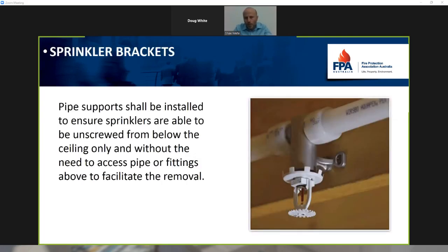A requirement for 101D is that pipes, well, the big issue here is once the construction is complete, if for whatever reason we need to remove a sprinkler, we need to be able to do that from below the ceiling. We don't want to be cutting holes in the ceiling to hold against and put a Stilson's or a spanner up there and hold against so that we can unscrew the sprinkler. The fixing must be that we can unscrew it from below the ceiling.